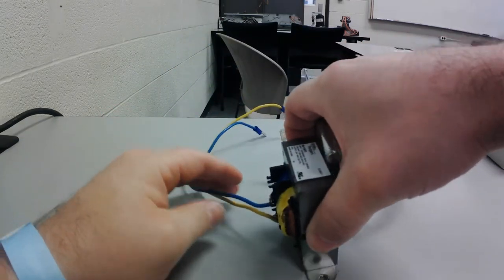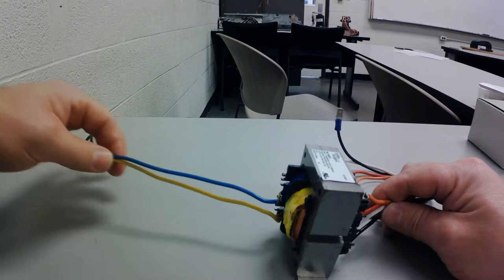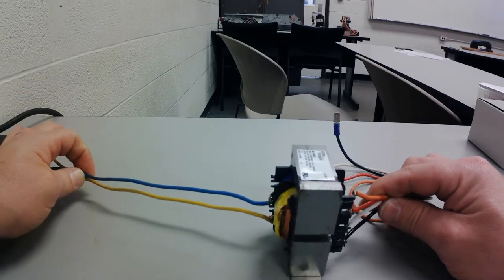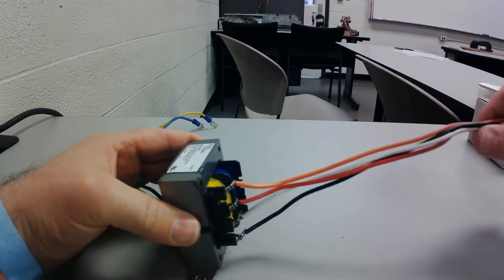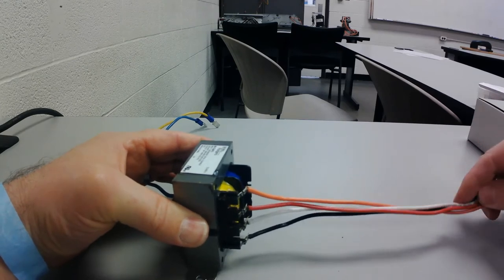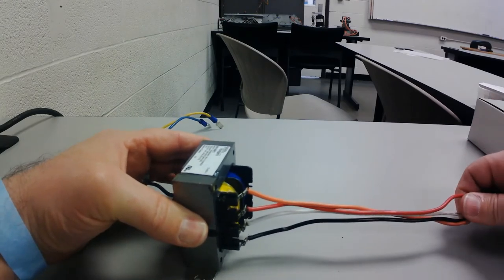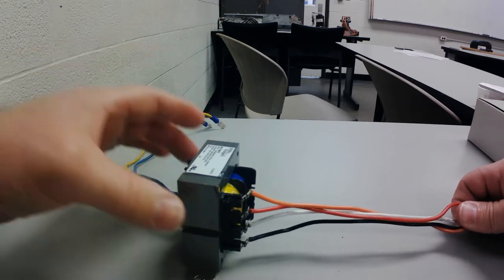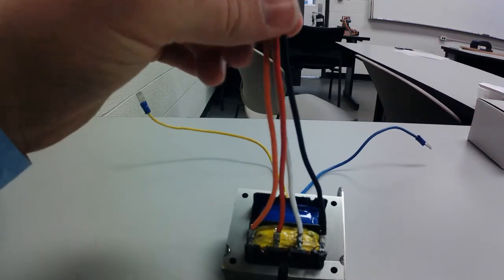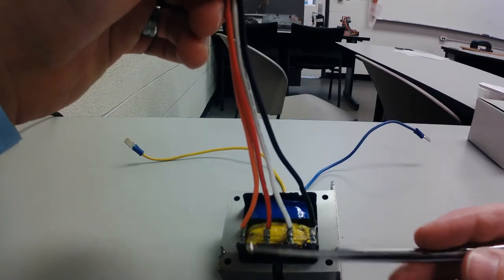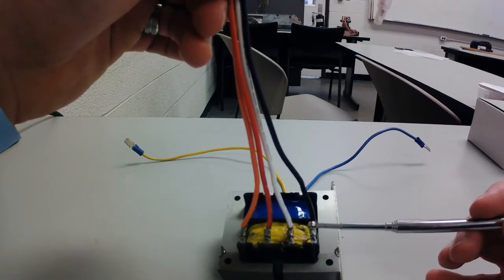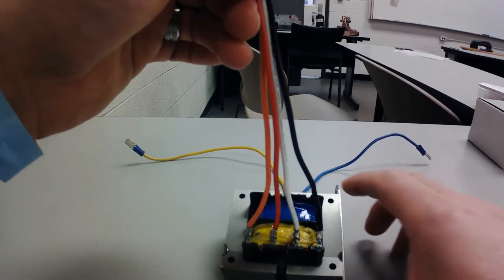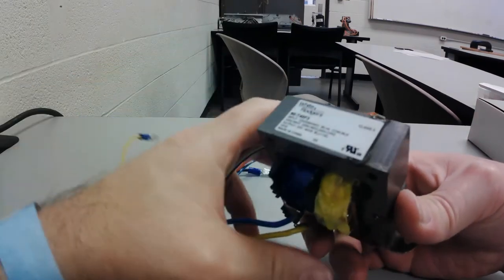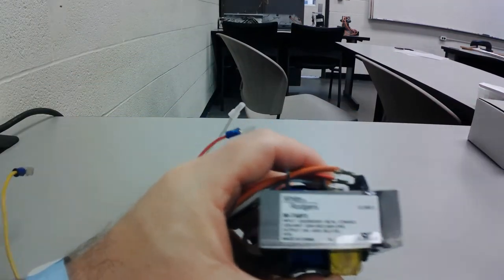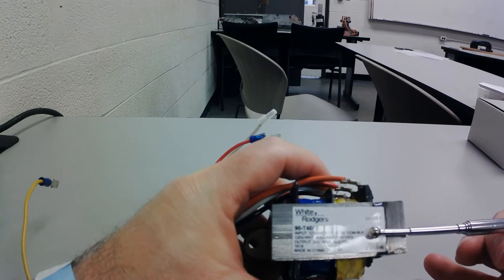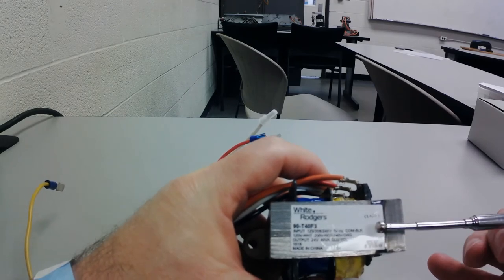So as we look at this, these wires over here, my blue and my yellow, that's my 24 volt. And then all these wires over here are going to be my primary side, my input voltage, in order to get that 24 volts out. So as we look, you can see that I've got orange and red and white and black. And you have to look at the data plate in order to know what wires you need to use.